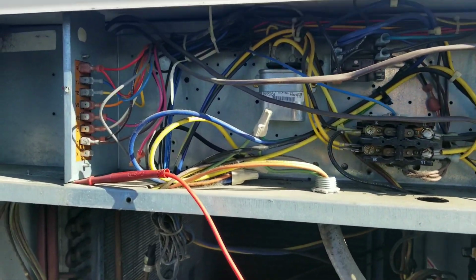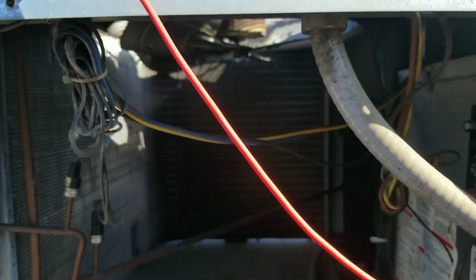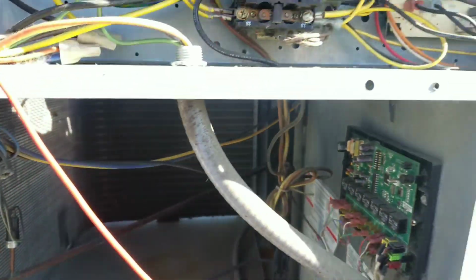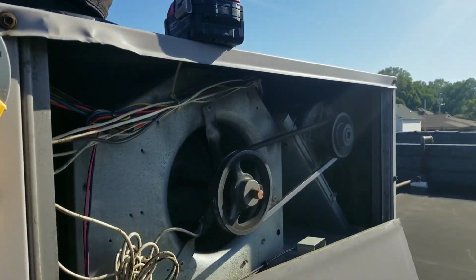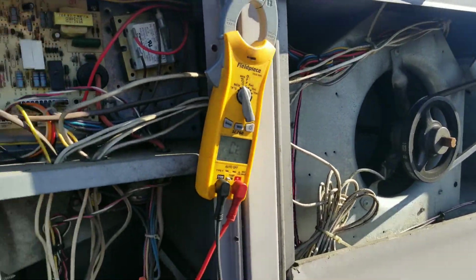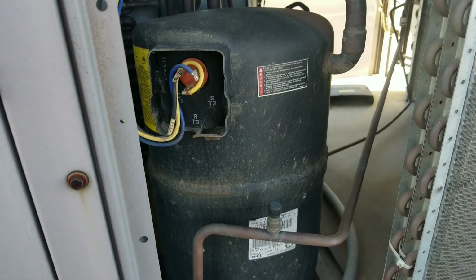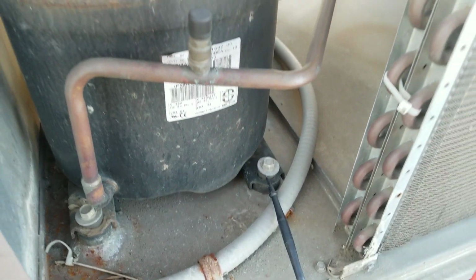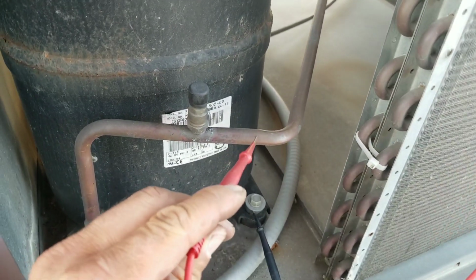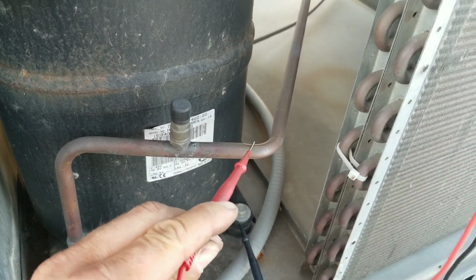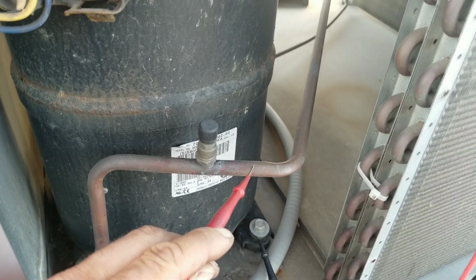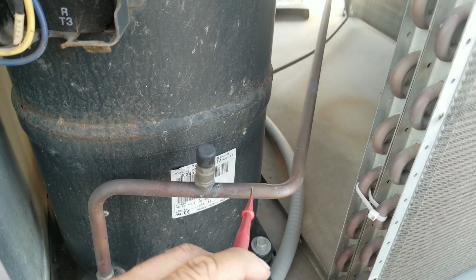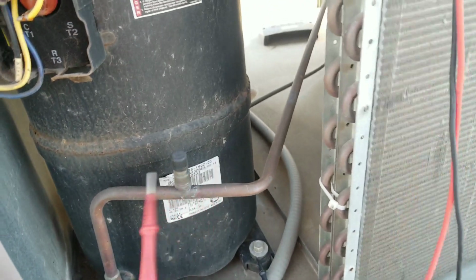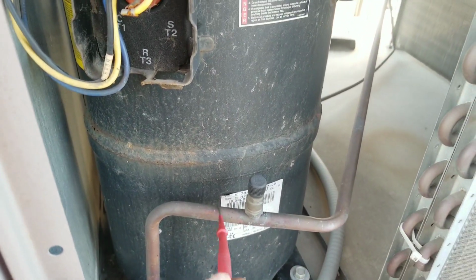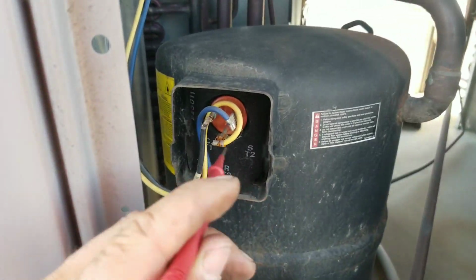So anyway, no shorts to ground over here, so I'm gonna pull that panel off the compressor over there, double check that, and then we'll also double check our blower motor as well. All right. Here's our compressor, guys. I got one lead just attached to the bolt, which goes to ground. If you listen, I am grounded at my copper line. Now that's all right to be grounded right there, but we're gonna check right here.